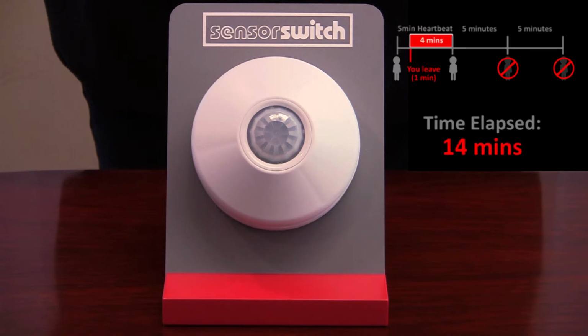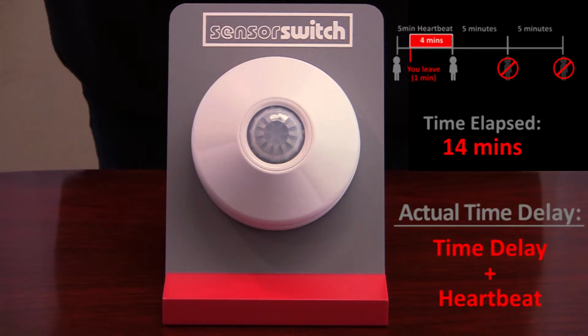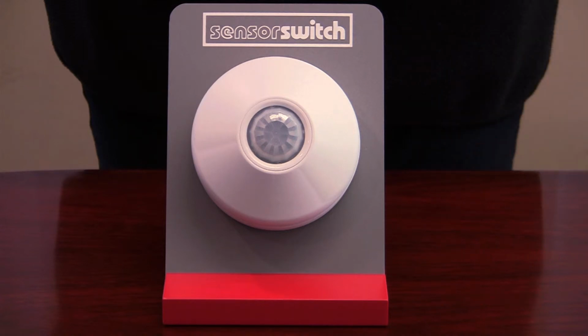As a rule of thumb, assume the actual time delay is the time delay setting added to the heartbeat setting. In this case, a 10-minute time delay and a 5-minute heartbeat means it can take up to 15 minutes for the lights to turn off. The wireless sensor has an estimated battery life of 10 years at the default settings. Changing the heartbeat to less than 5 minutes will reduce battery life.